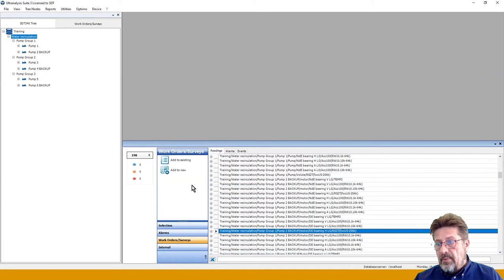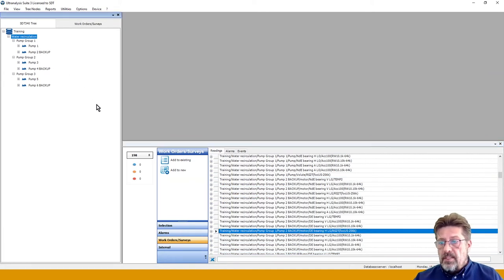And let's hypothetically put another situation here. I have a technician, a process technician, who is sometimes checking valves and all the other stuff, and I can easily ask him, can you please just check the body of the pump, the volute, for cavitation, while you are playing with the valves? Why not? Probably he will say, nah, don't push me into the bearing, that's not my job. But of course, easily I can put the sensor and listen to cavitation and collect data. That's a great job, because I will be playing with valves anyway.